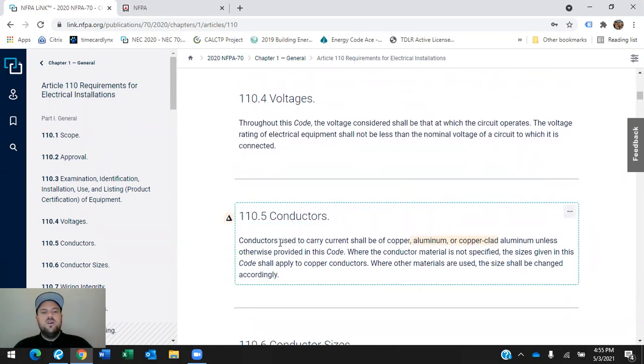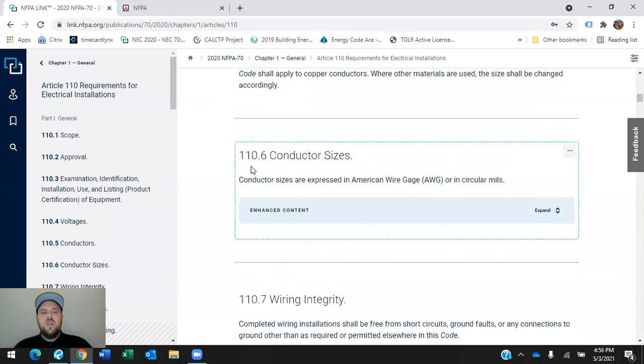110.5, conductors: conductors used to carry current shall be of copper, aluminum, or copper-clad aluminum unless otherwise provided in this code. Where the conductor material is not specified, the sizes given in this code shall apply to copper conductors. Where other materials are used, the size shall be changed accordingly.